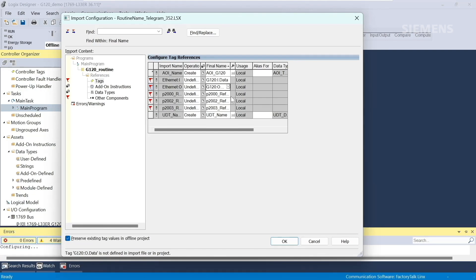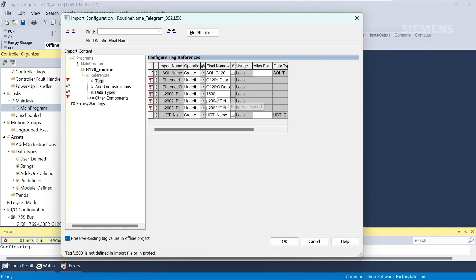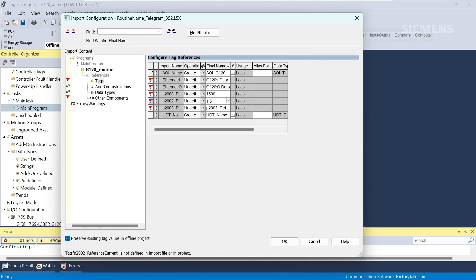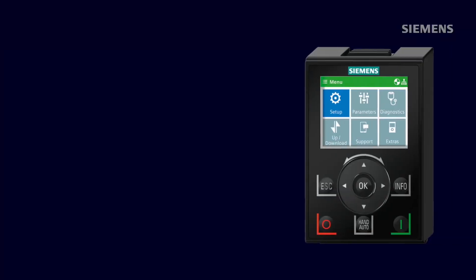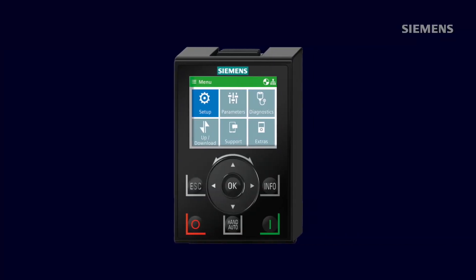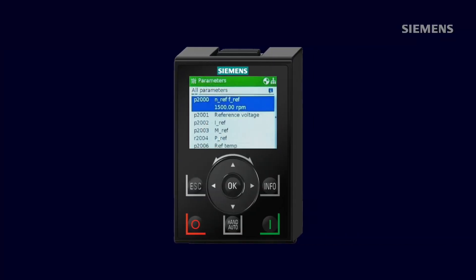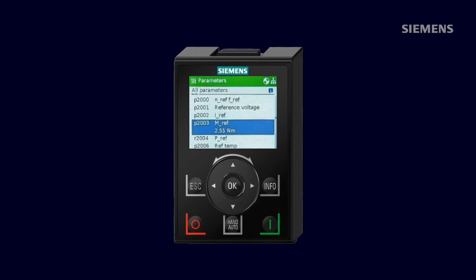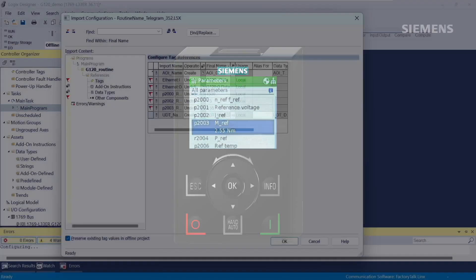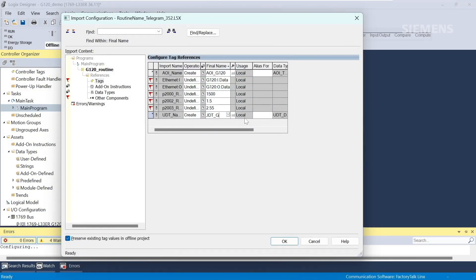We must enter the value of parameter 2000 for reference speed. In this case, I used 1500 RPM when I commissioned the drive. Next, I'll enter the value of parameter 2002, reference current, and enter 1.5 amps, and then the reference torque of 2.55 Newton meters. If you need to verify these values, you can use the drive's operator panel and see the values in these parameters. Then we can rename the UDT. We'll call it UDT G120.